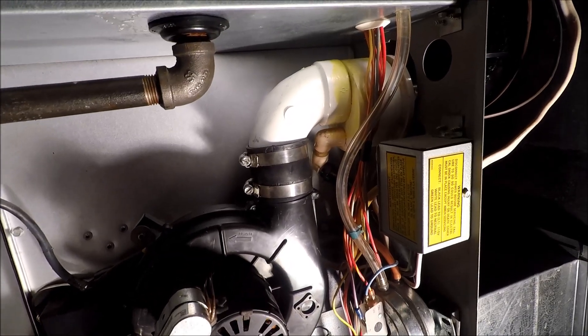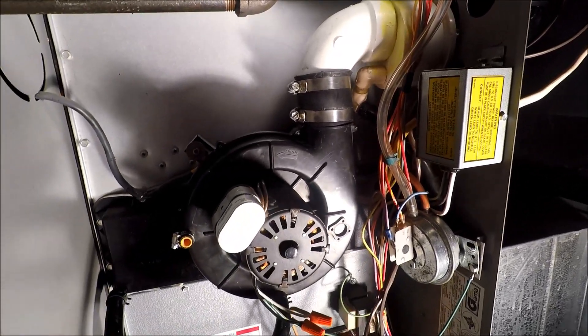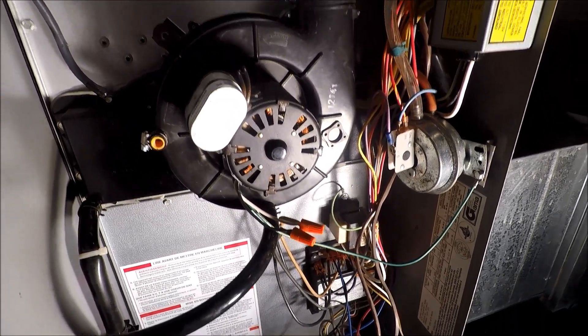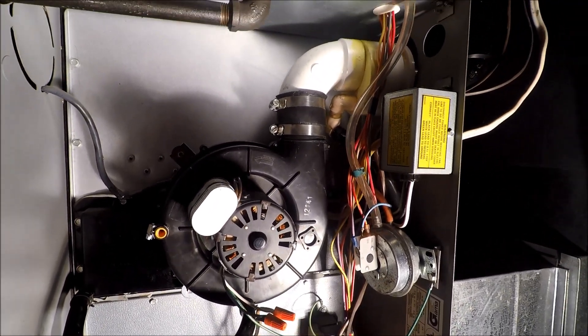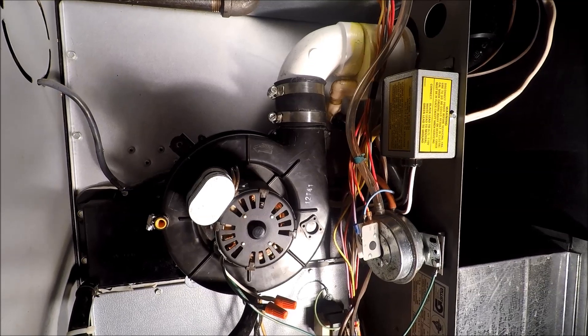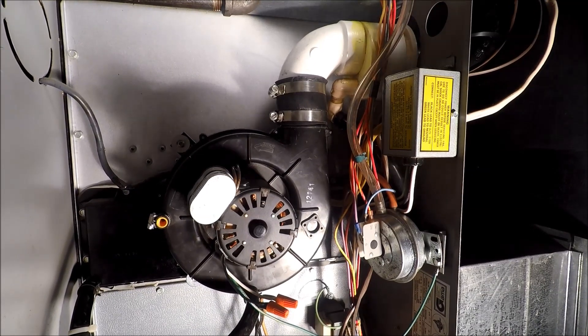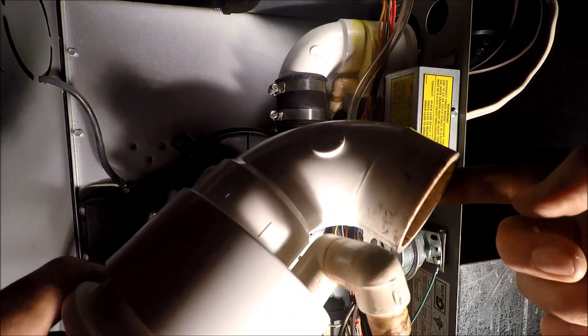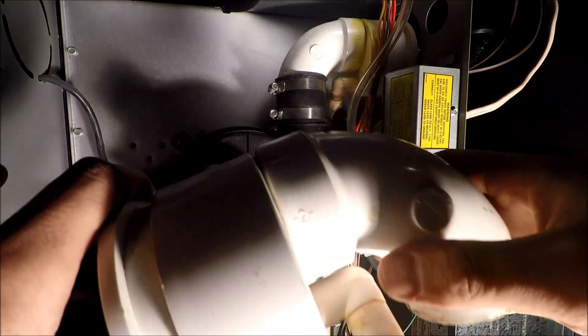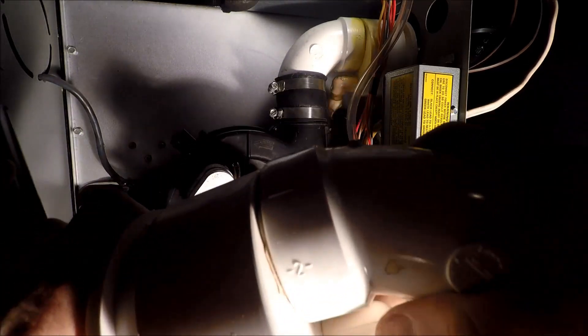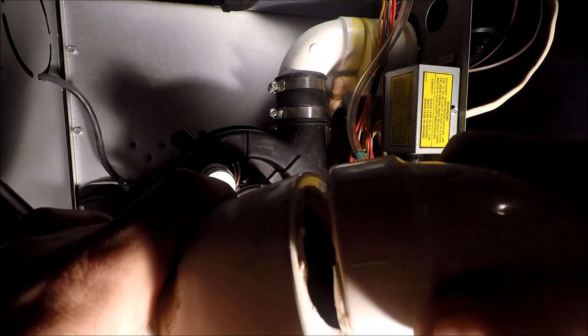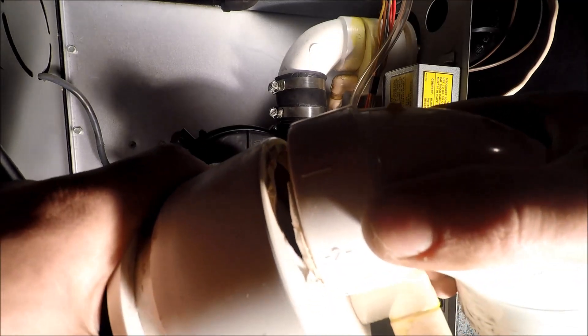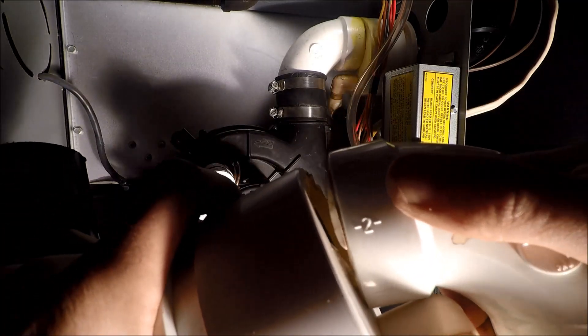Here's after we have it all cleaned up and installed, changed the Marrettes, put the pipe clamps on. And under further investigation when I was taking this apart, this is where the exhaust comes out, moisture leaks down there, it's like a little condenser. I discovered that, and I'll let the fumes into your house.